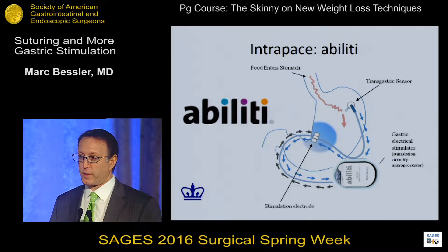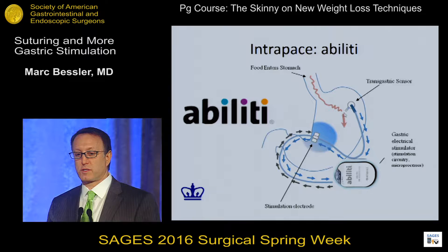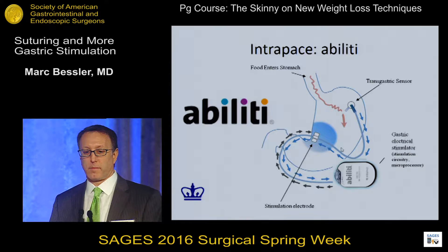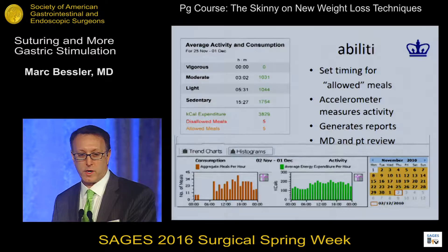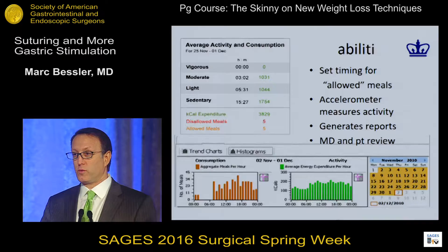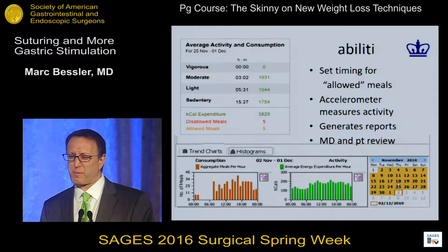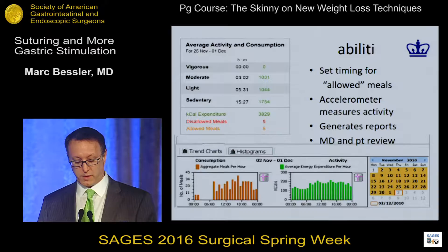Here's another interesting device called Abiliti by Intrapace. They've been working on various versions of this for a long time. The difference about this is it actually has a transgastric sensor — this device goes into the lumen of the stomach, and that detects when food comes in and stimulates only during that time, as opposed to the last device where it was separation of the electrodes by distention. It also has an accelerometer and can measure how much exercise the patient is doing — light, moderate, or vigorous. You can graph activity when you communicate with the device. With this device, you set times when you're allowed to be eating, you don't stimulate during those times, and you get noxious stimuli potentially if you're eating outside those allowed windows.